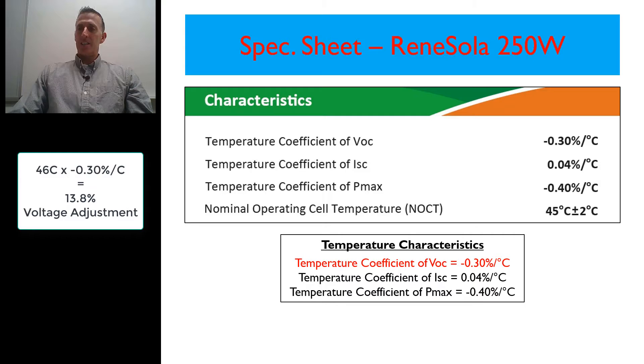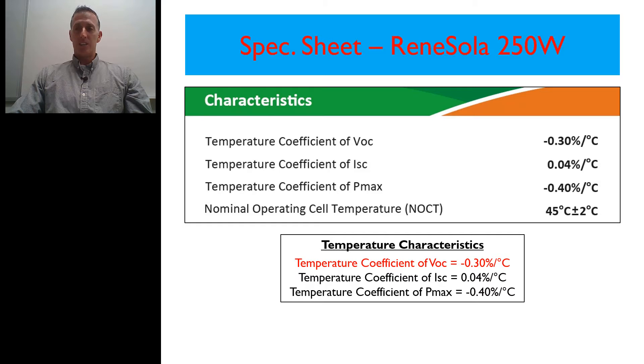That tells us that if you multiply 46 degrees by this number right here, negative 0.3%, we're going to have a temperature swing of just under 14%, meaning, or sorry, not a temperature swing, but you'll have a voltage adjustment of 14%. That would be an increase in voltage.